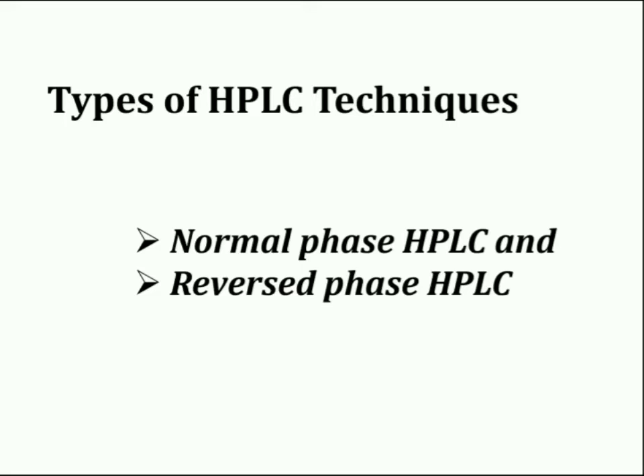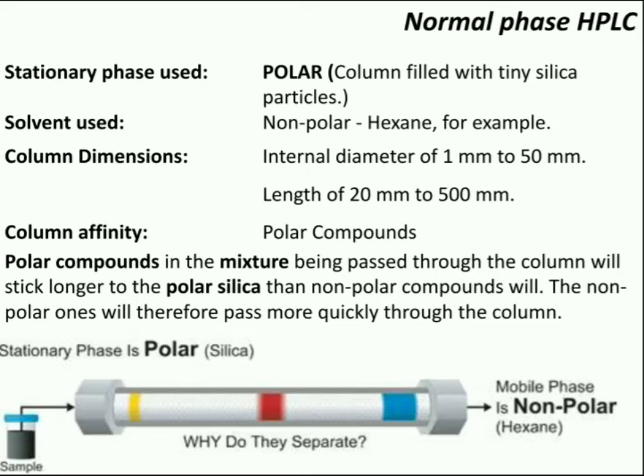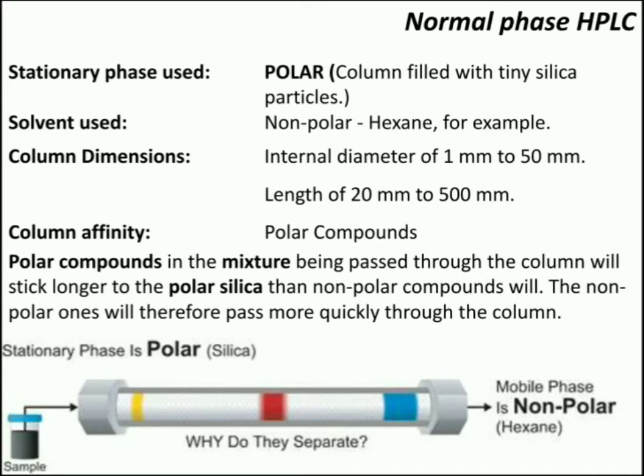HPLC techniques are of two types: normal phase HPLC and reverse phase HPLC. In normal phase HPLC, a polar stationary phase is used — it is usually a column filled with tiny particles of silica. The solvent used is nonpolar, for example hexane. Column dimensions used in normal phase chromatography are an internal diameter of 1 mm to 50 mm and a length of 20 mm to 500 mm.